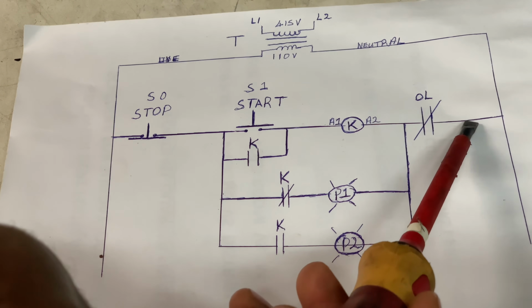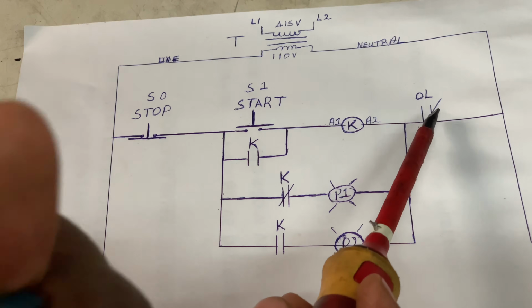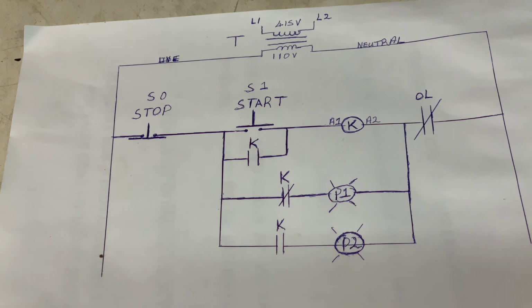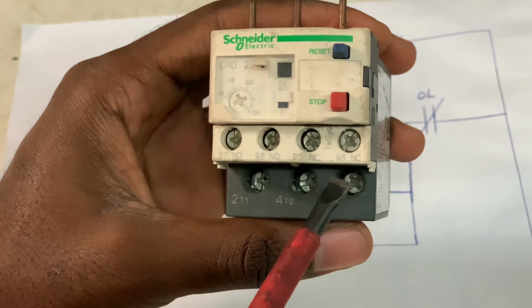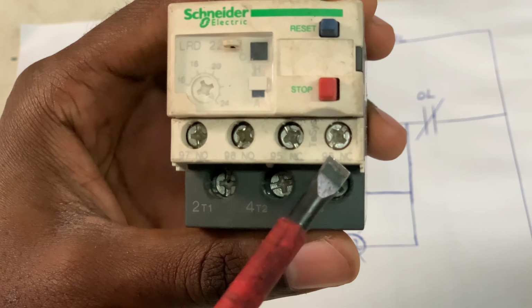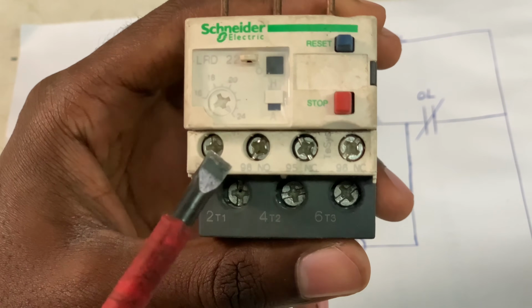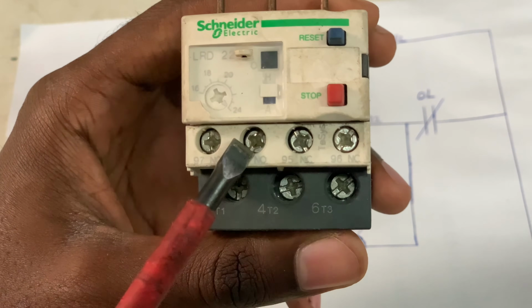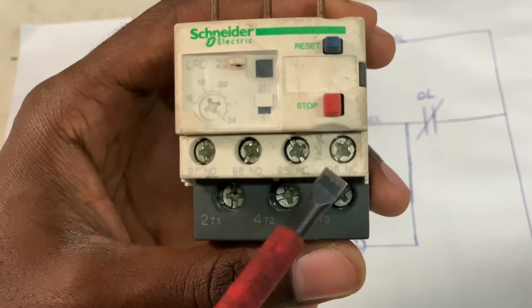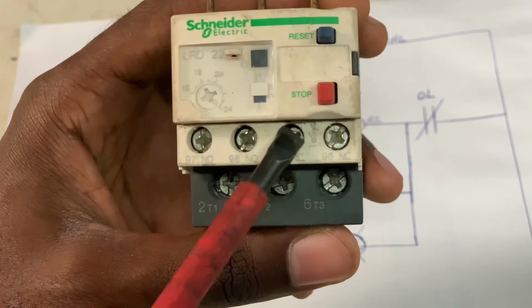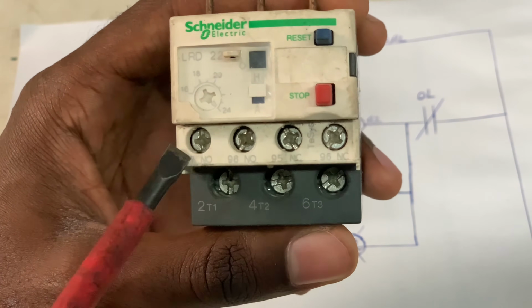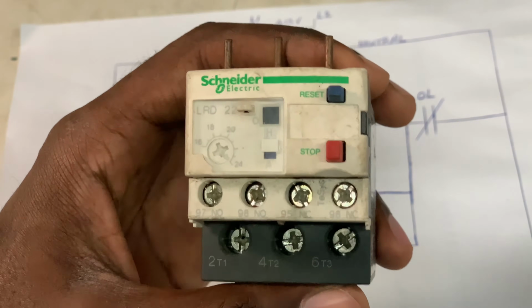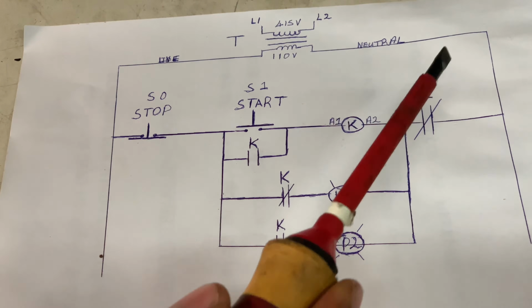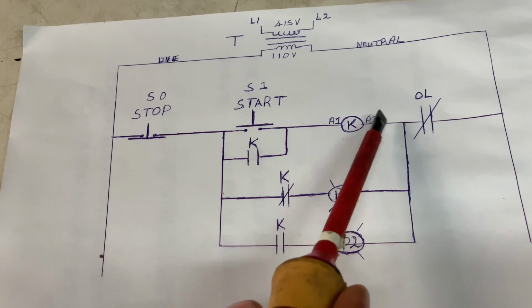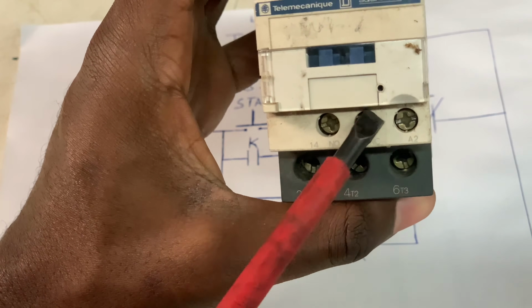Alright, so for the other side now, I took the neutral line and ran it to a normally closed pair of contacts on the overload. So this is the overload. On the overload you will see NC, which represents normally closed, right? And you will also see NO, normally open. So NC, which is 96 and 95. So this is the pair of normally closed, and this is the pair for the normally open, 97 and 98. Alright, so I run it through the normally closed pair of contacts on the overload, then to A2 on the contactor right here, A2.